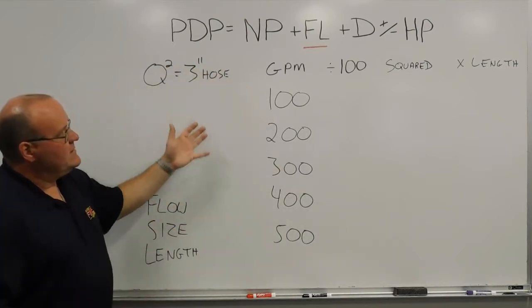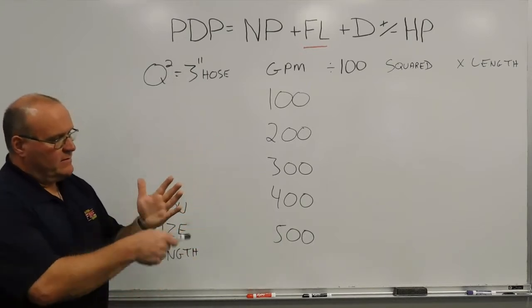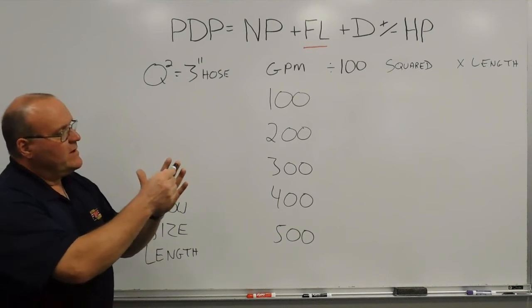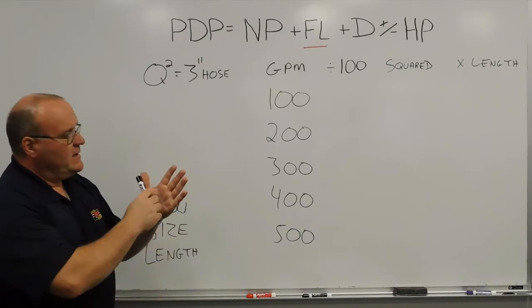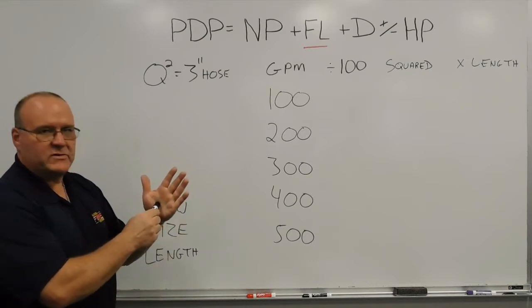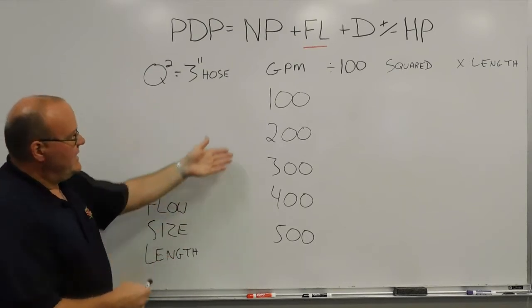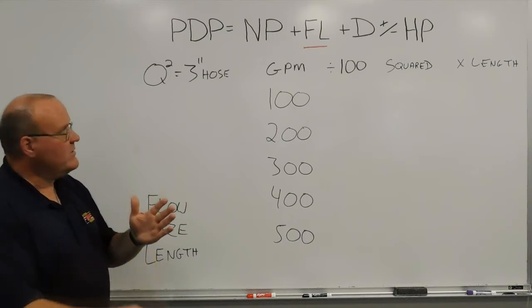So making this a hand method at 2 o'clock in the morning, you have your hand here, your hillbilly calculator, if you will. 100, 200, 300, 400, and 500 from left to right, thumb to pinky. And then the palm, you visualize a multiplication symbol, that gives you your squared. Staying within the realm of 500 gallons a minute, 1, 2, 3, 4, 5, 100, 200 to 500.